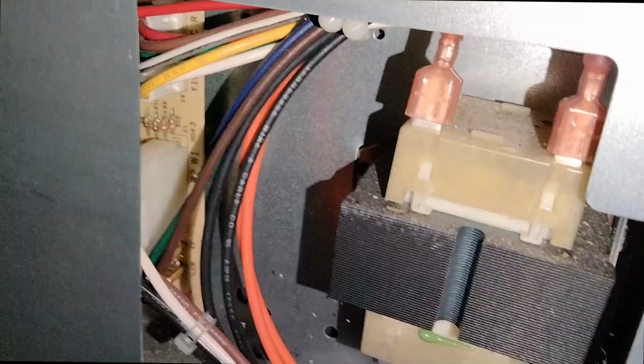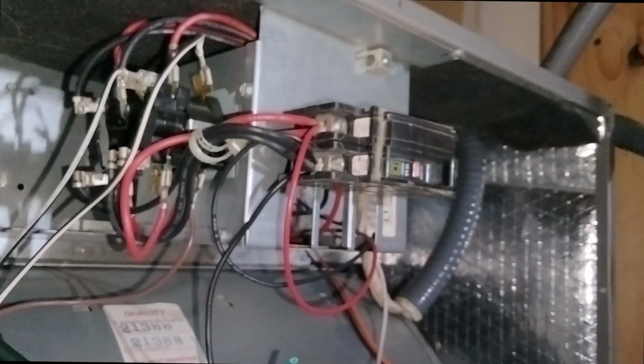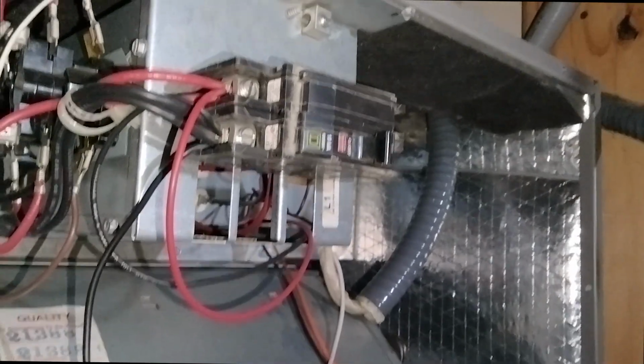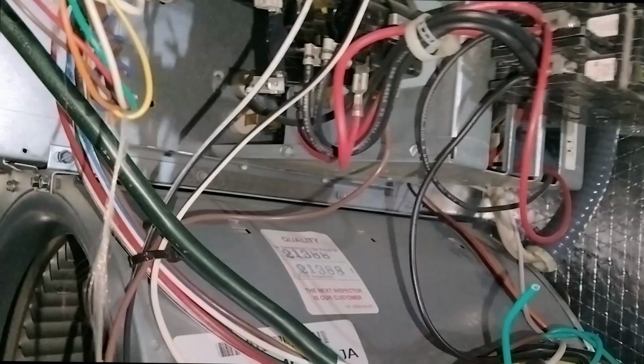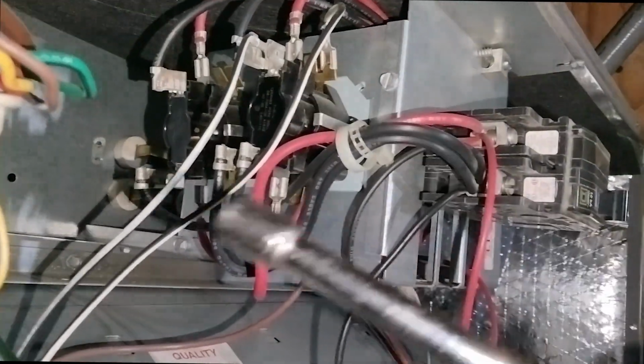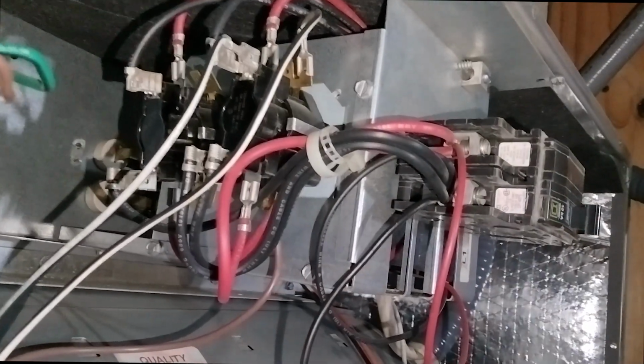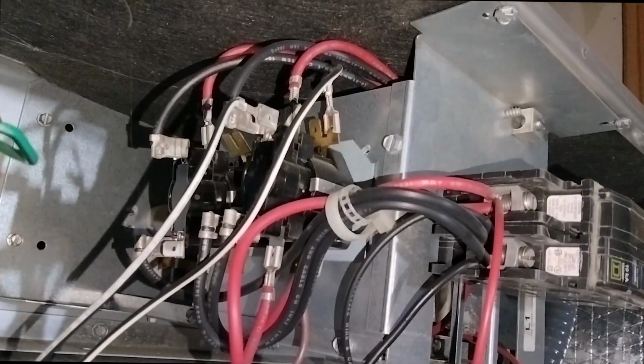The other option is that if you are hearing the relays and you've tested your sequencers, and it's at least making some sort of noise, potentially your motor might be bad, or your board is not sending the 24 volts to your motor. So what you need to find out here is back to the basics: making sure you do have power, that all of your relays are closing like they should, that your sequencer is closing and allowing that high side voltage through, and that there are no breaks in your wires.